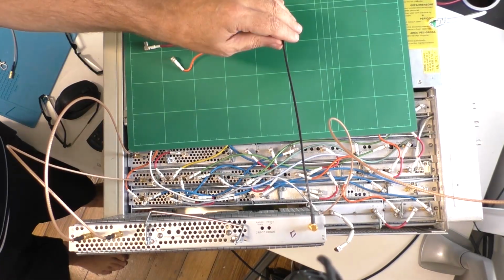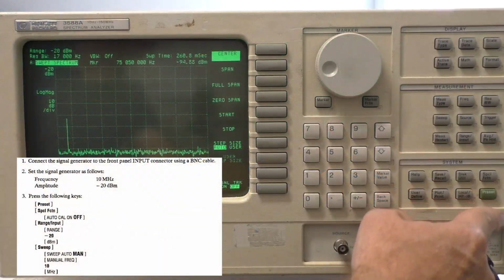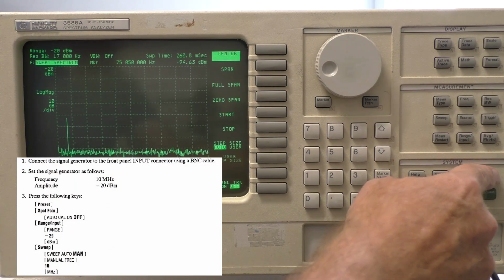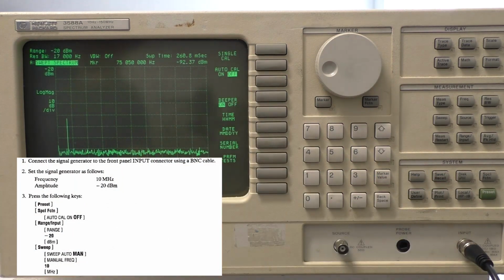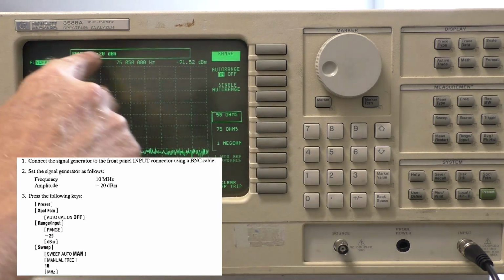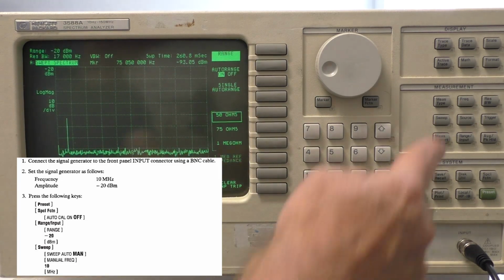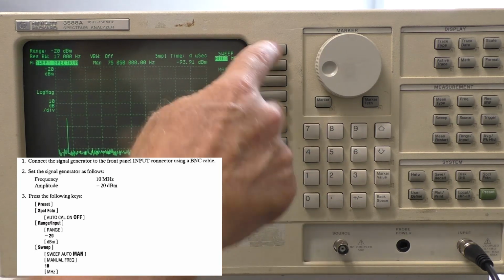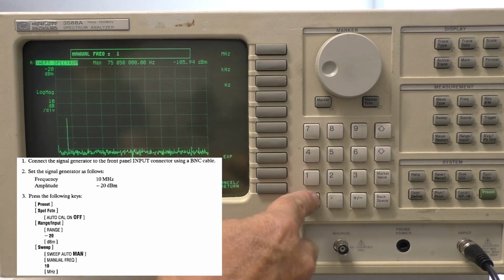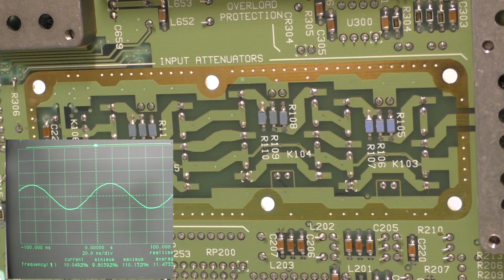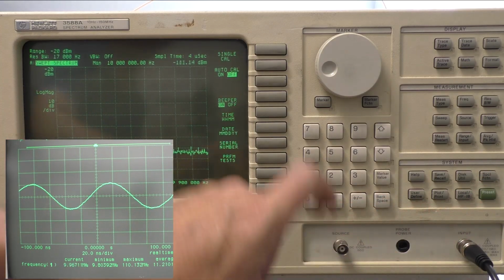Reconnect the oscilloscope to J3. Set the unit up as we did earlier. Hit preset. Special function. Auto cal off. Range input. Range. Enter -20 dBm. Sweep. Manual. Set the manual frequency to 10 MHz. Note the 10 MHz signal on the scope. Perform a single calibration as before. Hit special function. Single calibration.